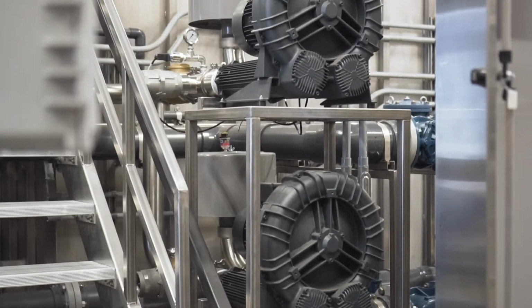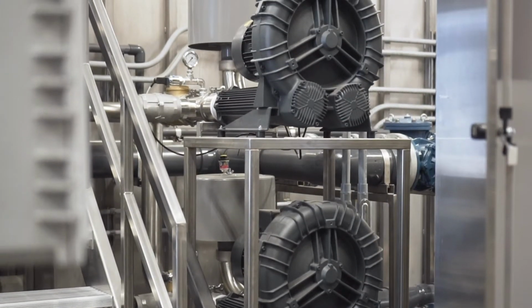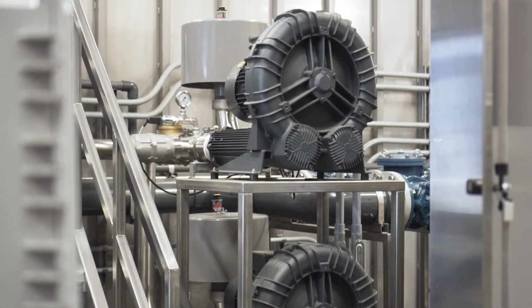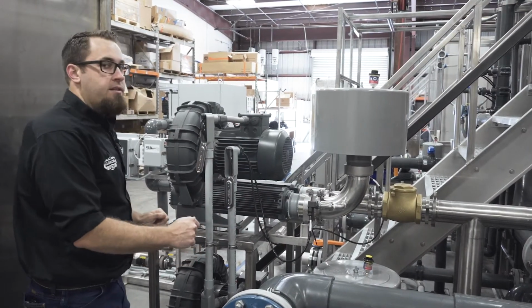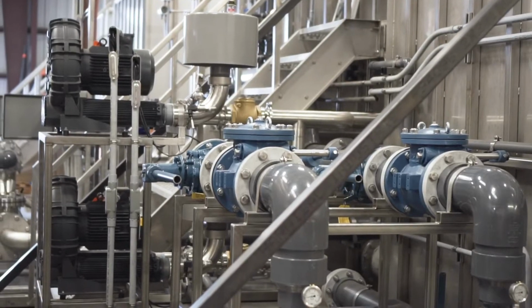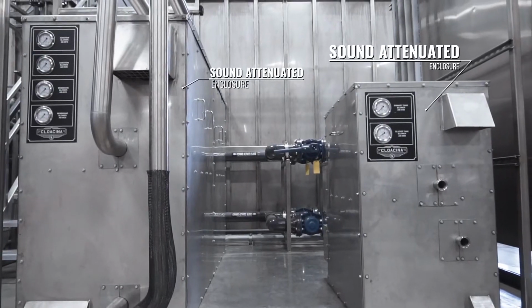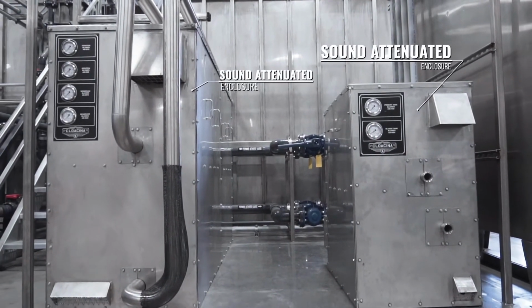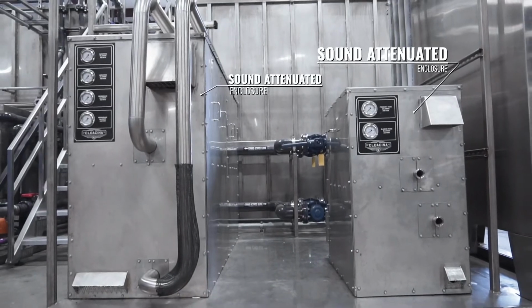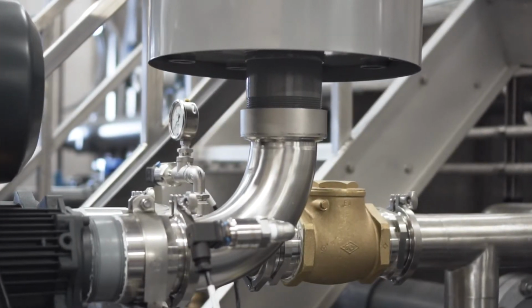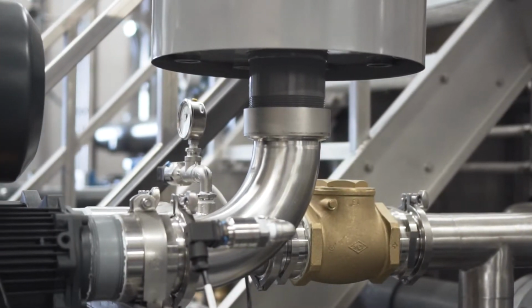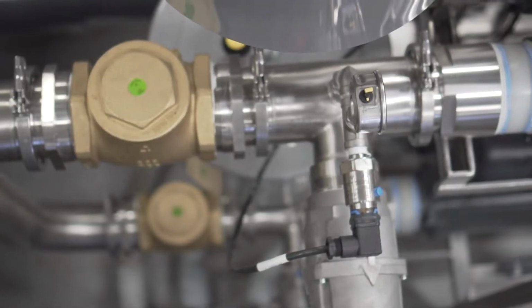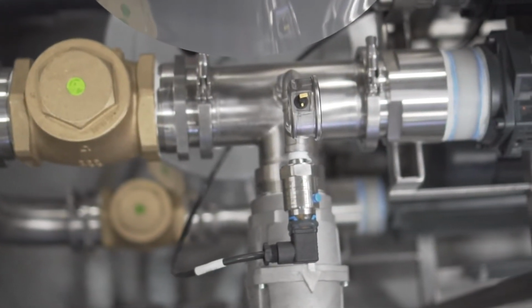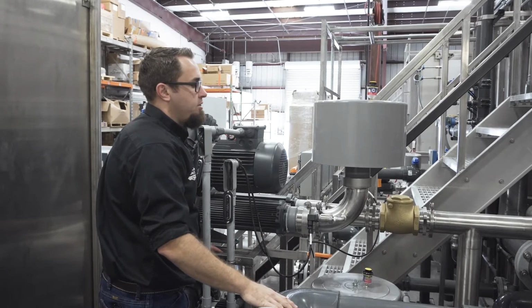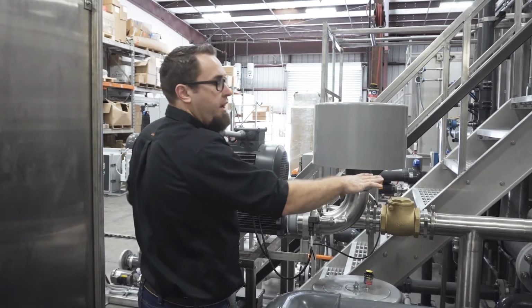Next thing I wanted to talk about was the way that we run all of our blowers and blower lines. Again, you'll notice everything is on a nice, neat, tidy stainless steel enclosure or support stand. We also manufacture these in sound attenuated packages. This particular client opted not to go with that. All of our suction and discharge piping is done out of 304 stainless steel, and it's welded in the exact same manner as sanitary fittings are for food and beverage applications. As a result, this will last forever.